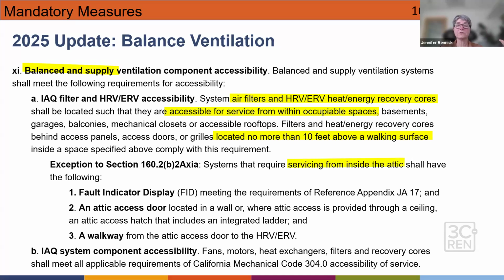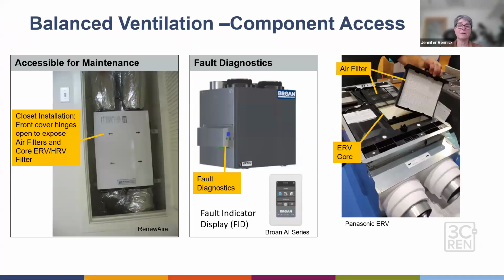You can, but there's some additional requirements, and that you need a fault indicator display. You have to have an access door that's located in a wall or through a ceiling, but that access hatch would include an integral ladder. And then you need a walkway from that access door to the HRV, ERV. So you could use it in an attic, but it has to be accessible, is the main thing. And so why is because there are things you need to do for these systems to maintain them. So the example on the right was a hallway closet installation. And so you can open the closet door, and then you can open the panel to access the ERV core and the filters.